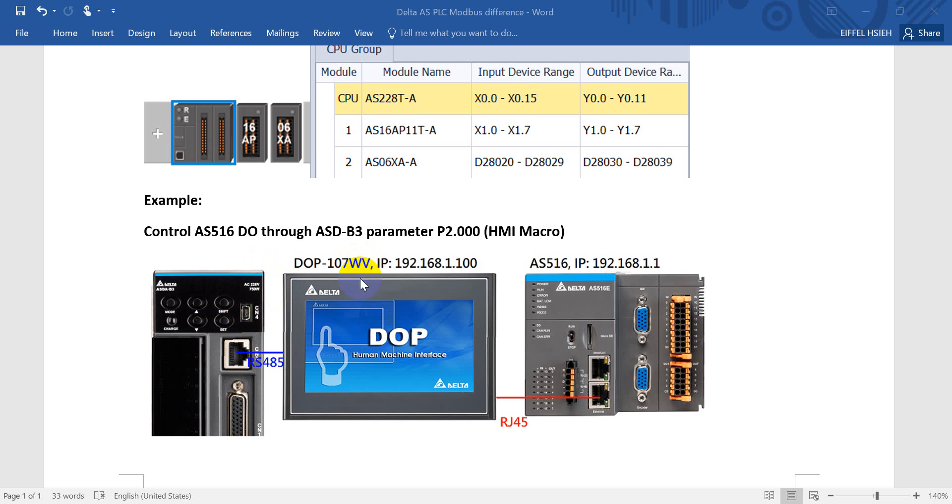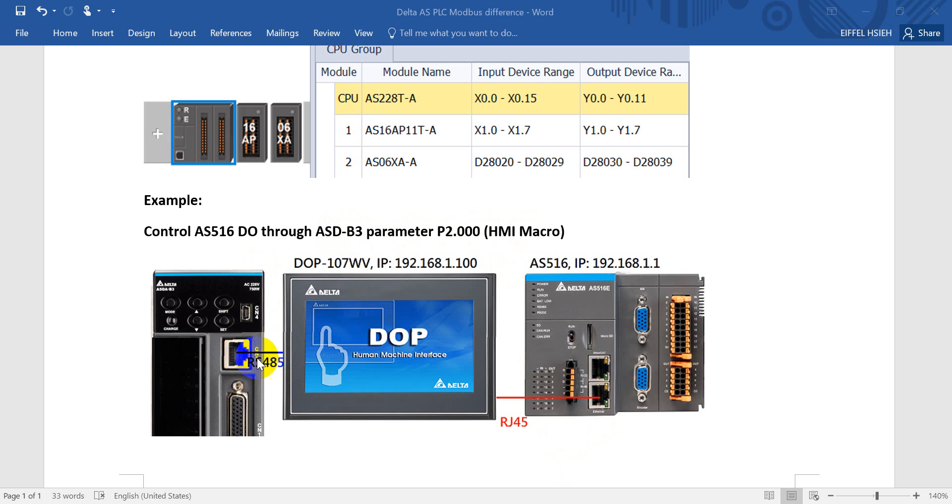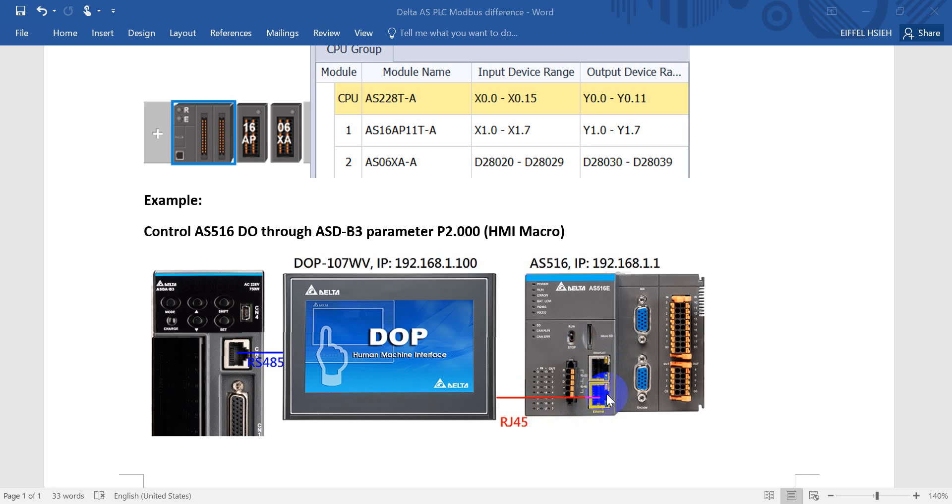And today's example I will use the parameter from a servo drive and we use the HMI macro to control the AS PLC output status. And here you can see we will use the RS485 link to the B3 servo drive and use the LAN cable Ethernet link with AS516. Just remind you this port is for EtherCAT, so for standard Ethernet we connect to this port.